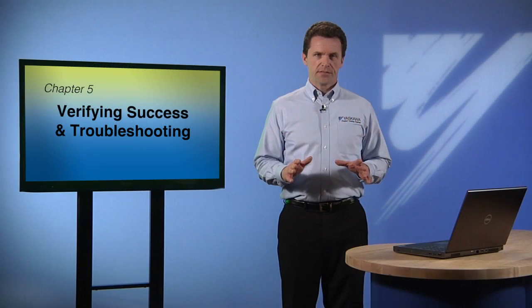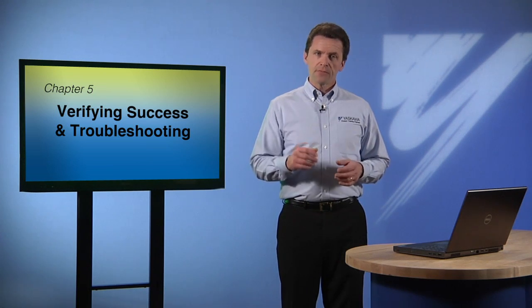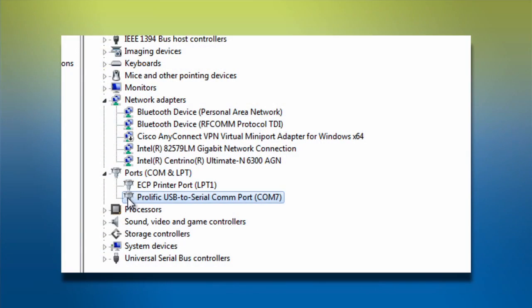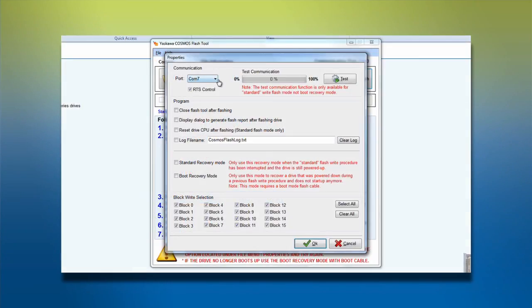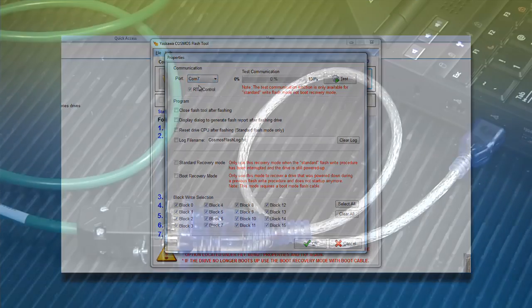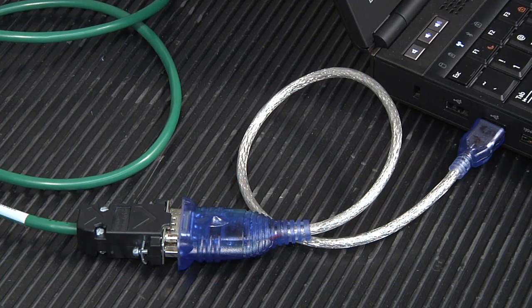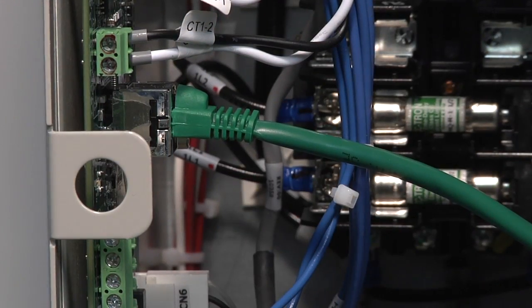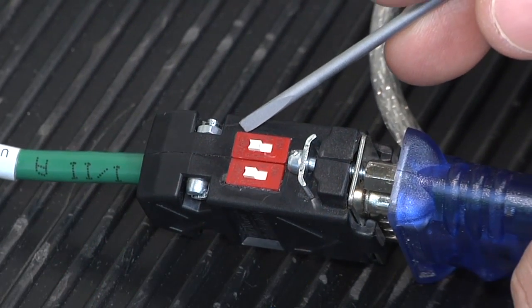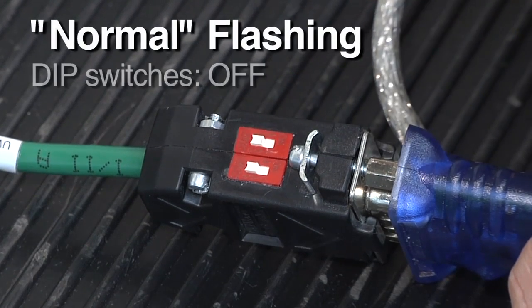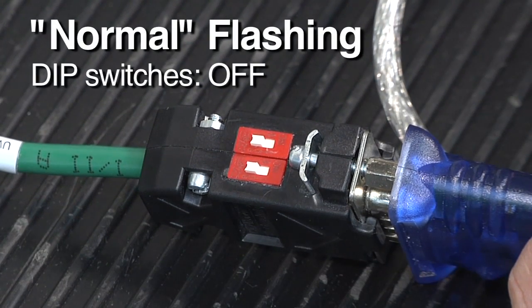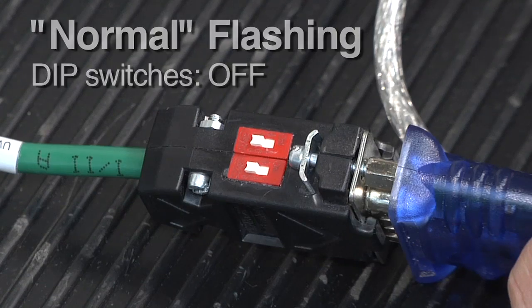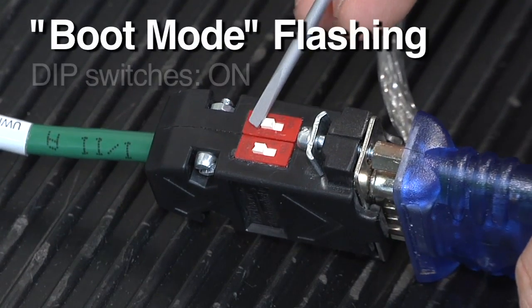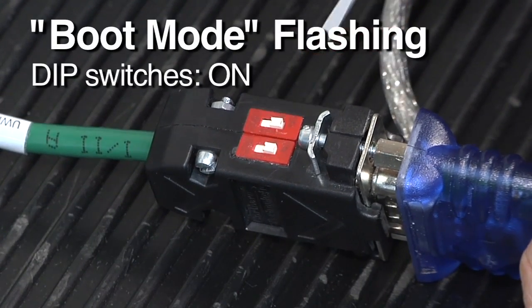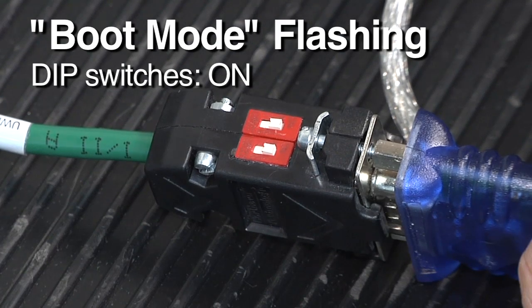If the flash process doesn't complete successfully, here are a few things you want to check to find out why. First, check to make sure the COM port number is correct. Also, look at the cable connections on the computer, the drive, and the bypass board to be sure they are properly seated. Check the dip switches on the connection cable as well, making sure that both switches are flipped to the off position for normal flashing. If you are trying to recover a drive from a previously failed flash attempt, both switches should be set to the on position for boot mode.